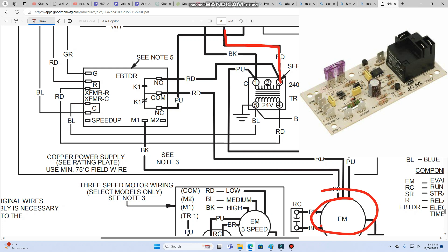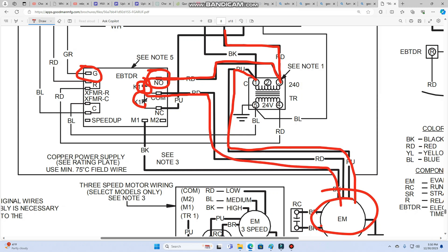So we have the power coming in from the electrical panel to the transformer. One of these legs are going right down to the blower motor itself directly. The other leg is being run through this relay here, and it goes to the normally open position. When the thermostat calls for the system to turn on, it powers this G terminal, which powers the coil. These switches reverse, and now our normally open closed. And it goes on from the comm terminal to the blower motor to complete both legs. 240 volts turns our blower motor on.